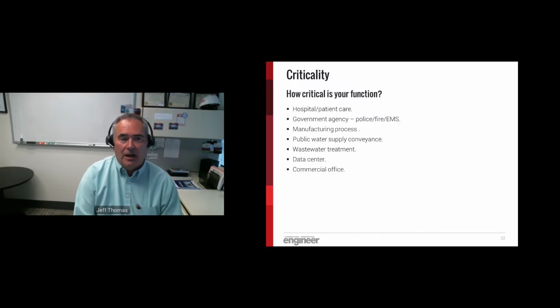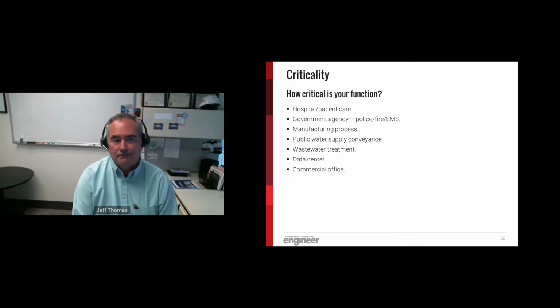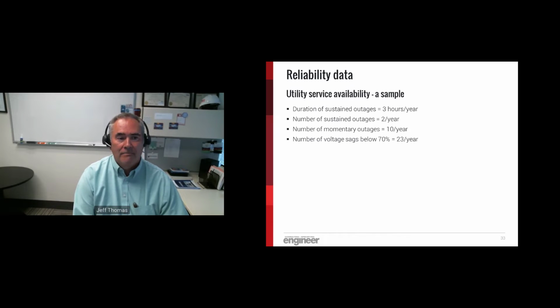So what you have to figure out is how critical is your function? Are you a hospital? Are you a commercial office? Or are you something in between? Only you can determine how critical you are. Some reliability data from utilities that will help you in your decision making. A utility typically says we go down 3 hours per year. We have 23 voltage sags below 70%. 70% is where typically equipment will drop offline. Can you tolerate those in your installation?